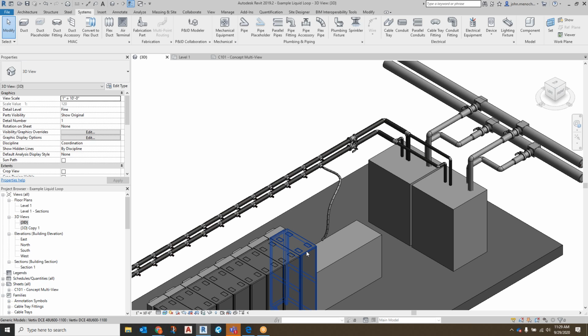So maybe the smallest liquid cooled cabinet might be 30 kW. How would you solve for a 30 kW application? But would you solve for one, or would you actually tap off your main header for, say, 8 of those as the minimum size of consideration? Because what you're seeing in the drawing, the cost risk factor is how many taps you actually want to put on your main loop.